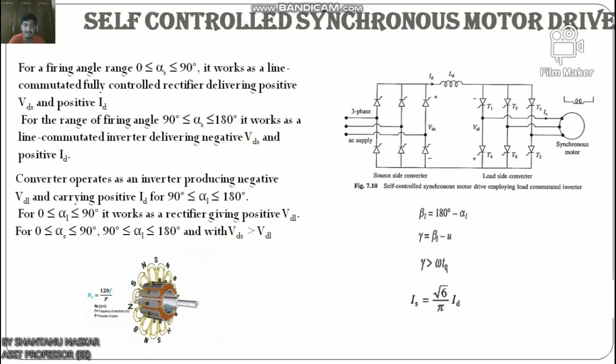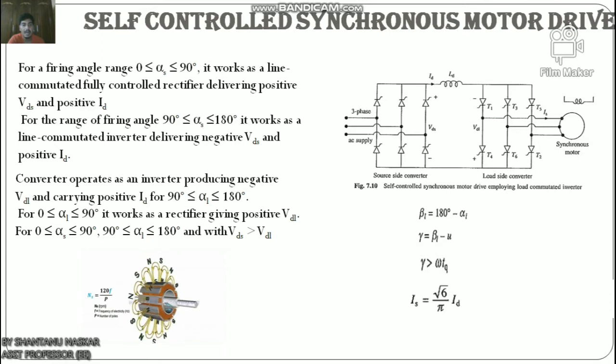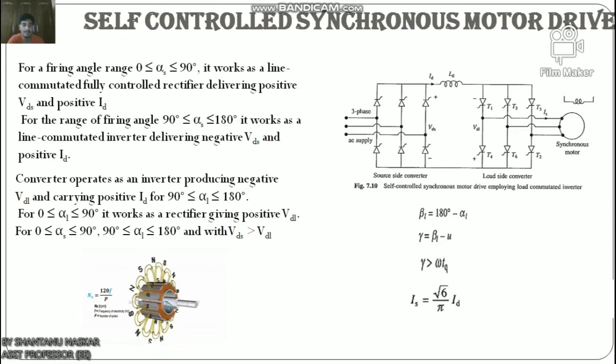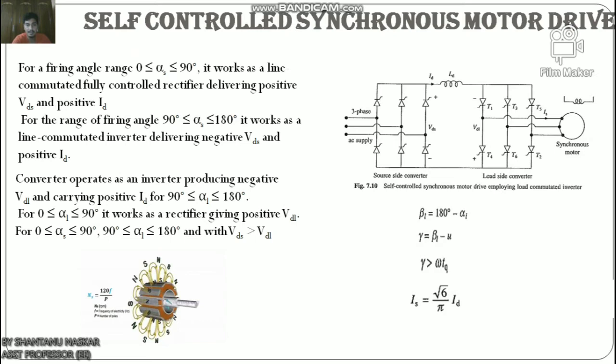If commutation overlap is ignored, the input AC current of the converter lags behind the input AC voltage by angle α1. Since the motor input current has an opposite phase to the converter input current, the motor current will lead the terminal voltage by angle β1; therefore the motor operates at leading power factor. A lower value of β1 gives a higher motor power factor and lower inverter rating. The commutation overlap for the load-side converter depends on the sub-transient inductance of the motor. The motor is provided with damper winding to reduce sub-transient inductance, allowing operation with a substantially low value of β1.